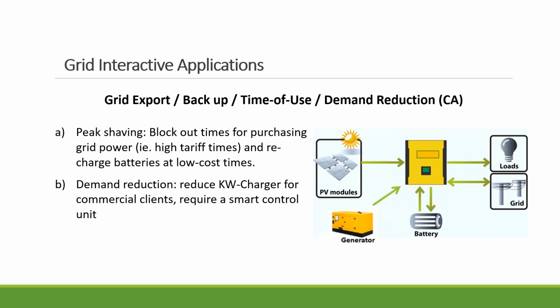Now, what's also getting more popular in certain areas is if you're subject to time of use, or if you have a high demand charge, the kW charge. If you look at your electrical bill, there's a space where, if you're subject to the kW charge, you will see that amount. For example, in New York State, the kW charge is very, very high. How does this application work? Basically, the hybrid inverter is smart enough that it knows when to block the time for purchasing grid power, and when to use the grid power or the PV power to charge the battery.